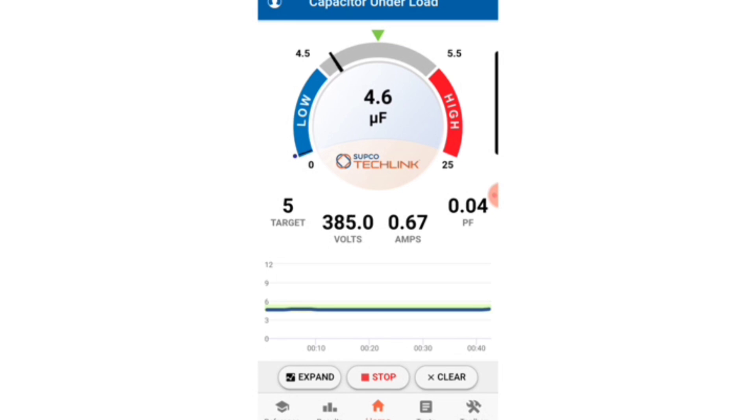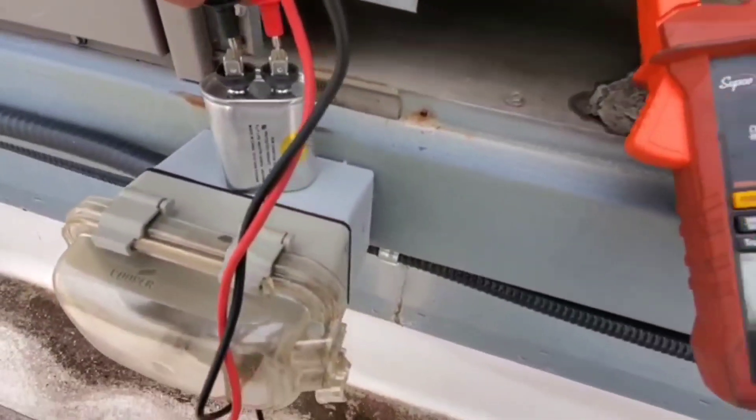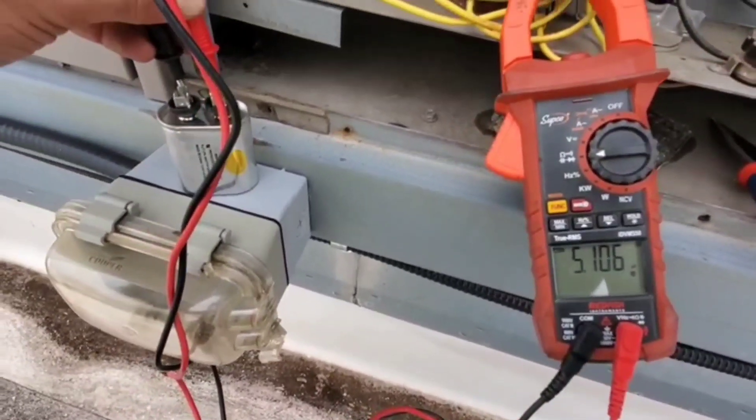That is actually outside of our 6% tolerance when it drops to 4.6, and this fan was having trouble starting earlier. So I'm going to go ahead and replace the cap and see if it makes a difference. I've got a brand new Supco gold seal cap there and I've got 5.1 microfarads. Let's put this in and see if it makes a difference.